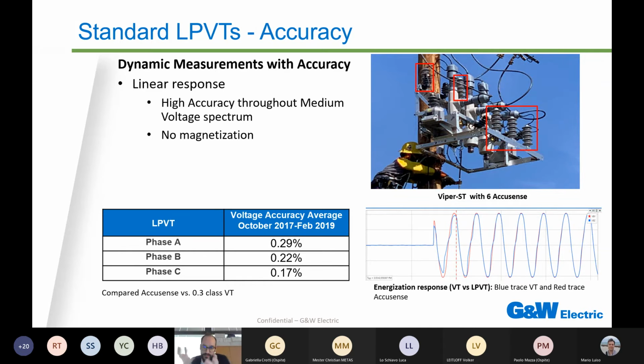The main strength of this technology is that they are very accurate, they do not suffer from magnetization, and they have a very linear response. So we are accurate through all the medium voltage spectrum. Below you can see the energization response of our sensor compared to a measurement voltage transformer, and you can see we do not suffer from saturation. So we have a very good representation of this transient.